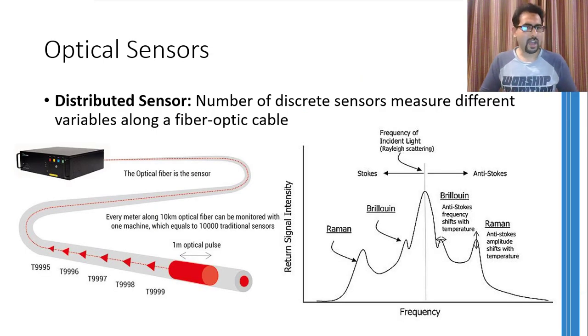Now the state of the art equipment is capable of processing a reflection generated after every one meter in the fiber optic cable. This means the time taken by the light to travel one meter is required by this state of the art equipment to process a reflection. Therefore, if light has traveled 10 kilometers, then the reflections generated after every one meter can be processed by this equipment. And hence the temperature can be measured.